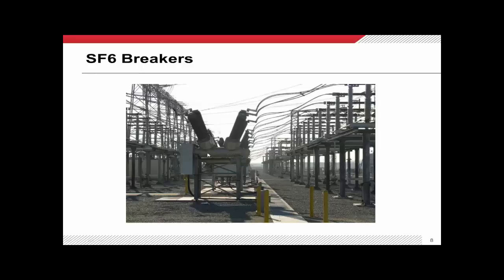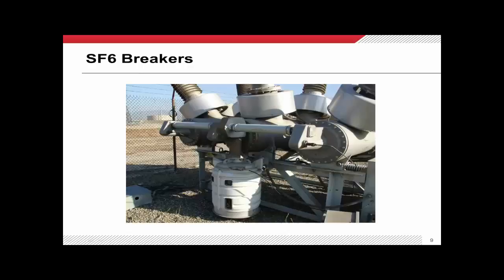This breaker is a 230 kV breaker but has the same exact principles — insulating medium inside the cylinders, interrupter inside, connects to two bushings on either side, and CTs inside the cowlings. A lot of the physical devices that make up the protection and control scheme are housed in the control cabinet. These breakers at 230 kV and below are mechanically linked together so all three poles operate in unison.